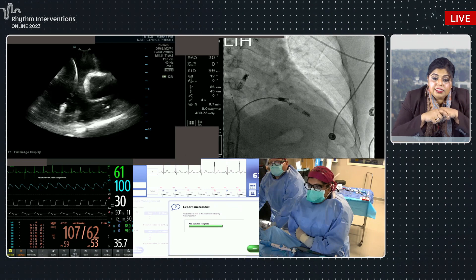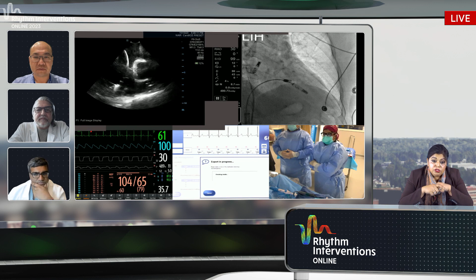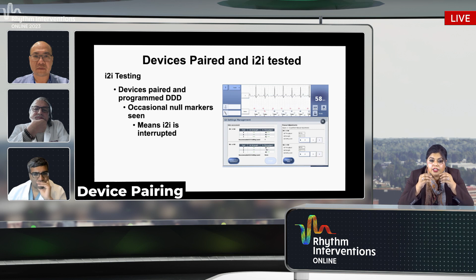And usually, at least currently, I tend to follow those recommendations, at least during the immediate post-implant phase. We'll see a dramatic difference in what the throughput and the i2i strength are, usually after the device is released and both devices are independent of tethers, and also the next day. I've seen a dramatic difference in the i2i and throughput as well. So this is i2i testing after they're paired. The device is programmed DDD in this case. You can see occasional null markers that tell you that the i2i is interrupted occasionally.